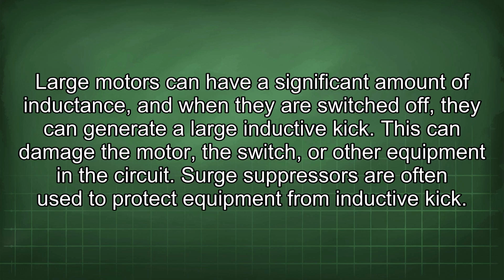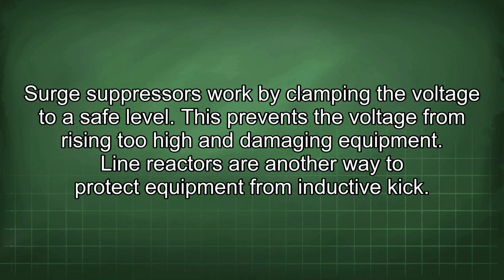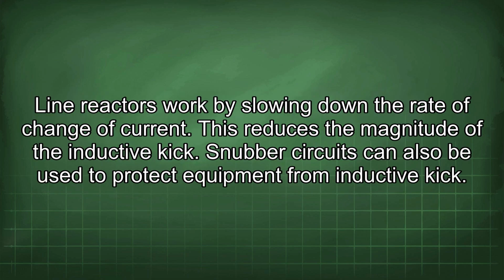Surge suppressors are often used to protect equipment from inductive kick. Surge suppressors work by clamping the voltage to a safe level. This prevents the voltage from rising too high and damaging equipment. Line reactors are another way to protect equipment from inductive kick. Line reactors work by slowing down the rate of change of current. This reduces the magnitude of the inductive kick.